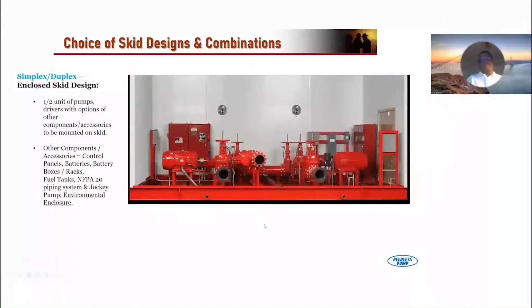We can even go one step further if you want us to put everything inside an enclosure. We can put a duplex package, electric and diesel drive, inside an enclosure with all the wiring, everything done per NFPA code. We ensure the pump is protected from the elements like ice, snow, rain, and dust. You can see it also has its own drain for when the pumps are running, since you'll have drain coming from the glands. This one is on the electric side, and these are 2 electric driven units, so we can put that on a skid like that.